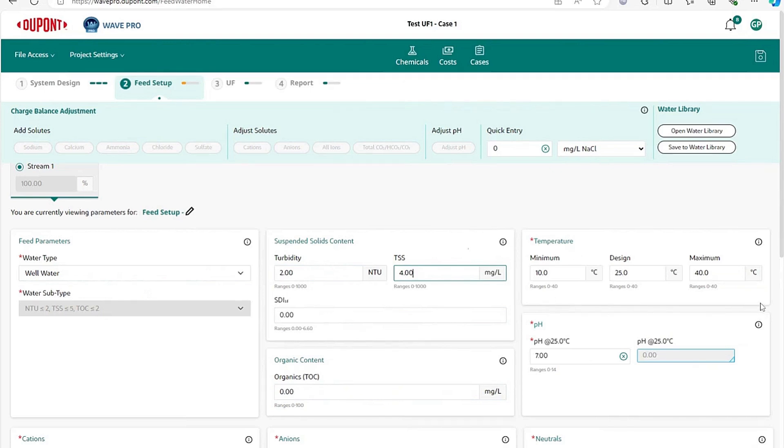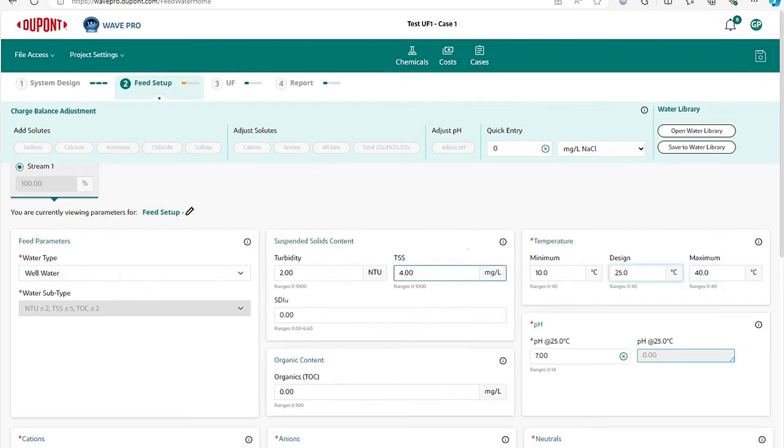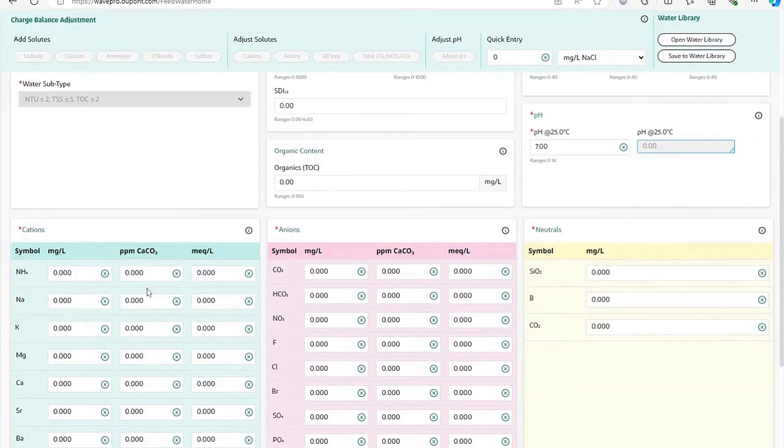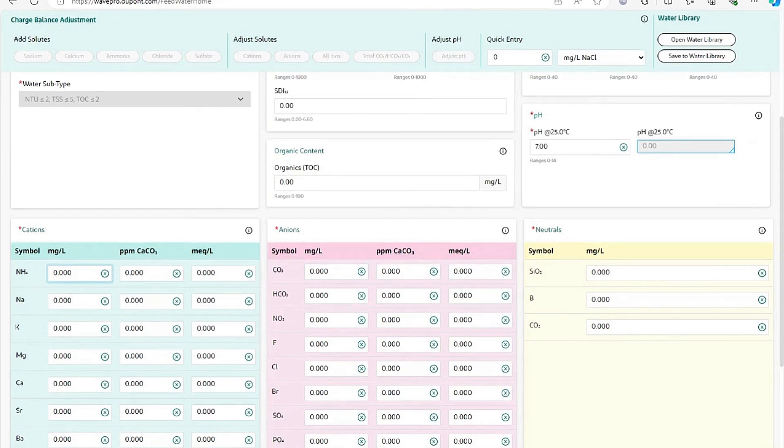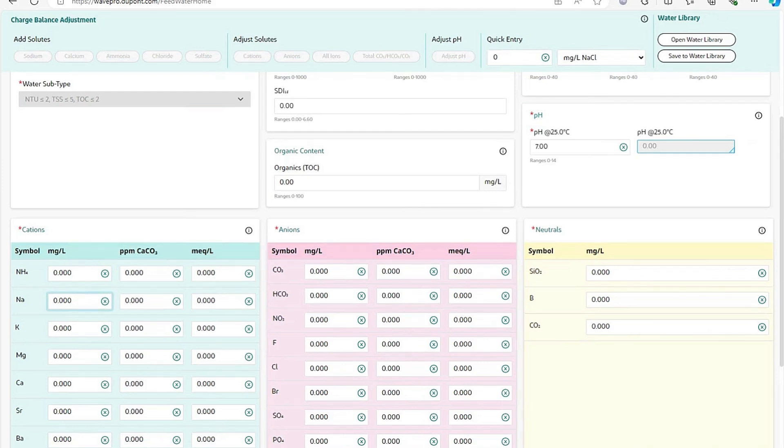Next, you would enter other parameters about your feed water. For example, the temperature range between your minimum, your maximum, and your design temperature, your pH, and then at the bottom here you would enter your water composition. Well, ultrafiltration does not necessarily need to have all of the feed water composition parameters entered. It is usually a good idea to do so because then you will get more accurate estimation of chemical demand for pH adjustments.